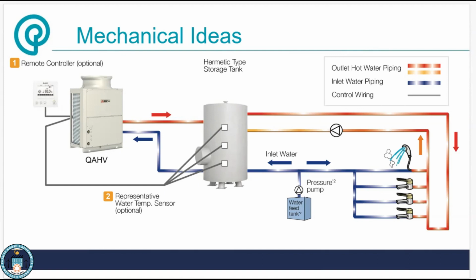And then these are a much more straightforward system where there's an outdoor unit and then there's an indoor storage tank, and you have to pipe water between the two. So instead of refrigerant, or CO2 in this case, being the refrigerant coming inside the building like you'd have with the split VRF system, all of the water heating happens in the outdoor unit, and that hot water is piped into the tank on the indoor unit.